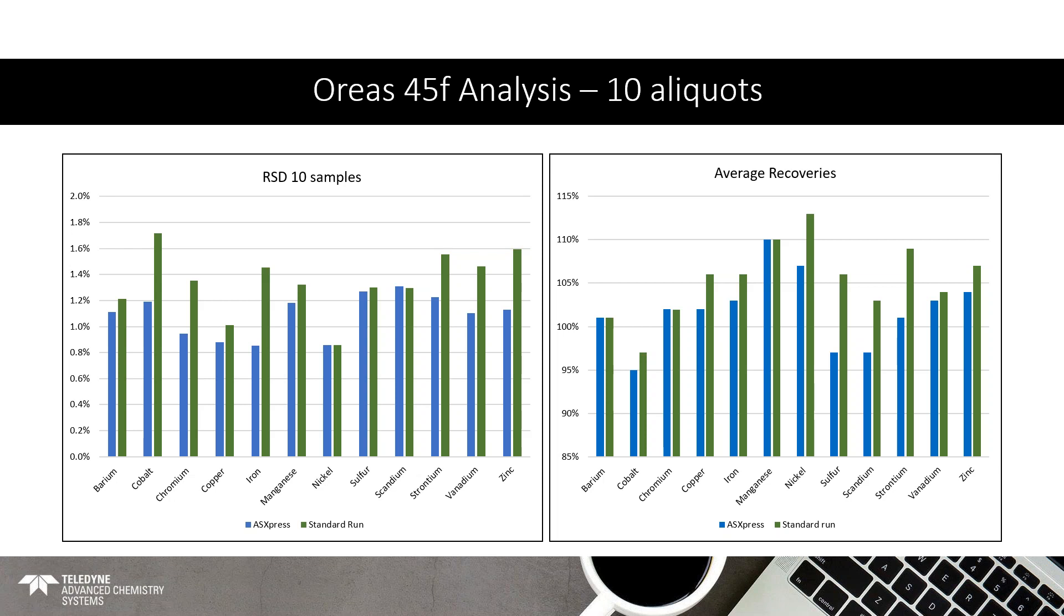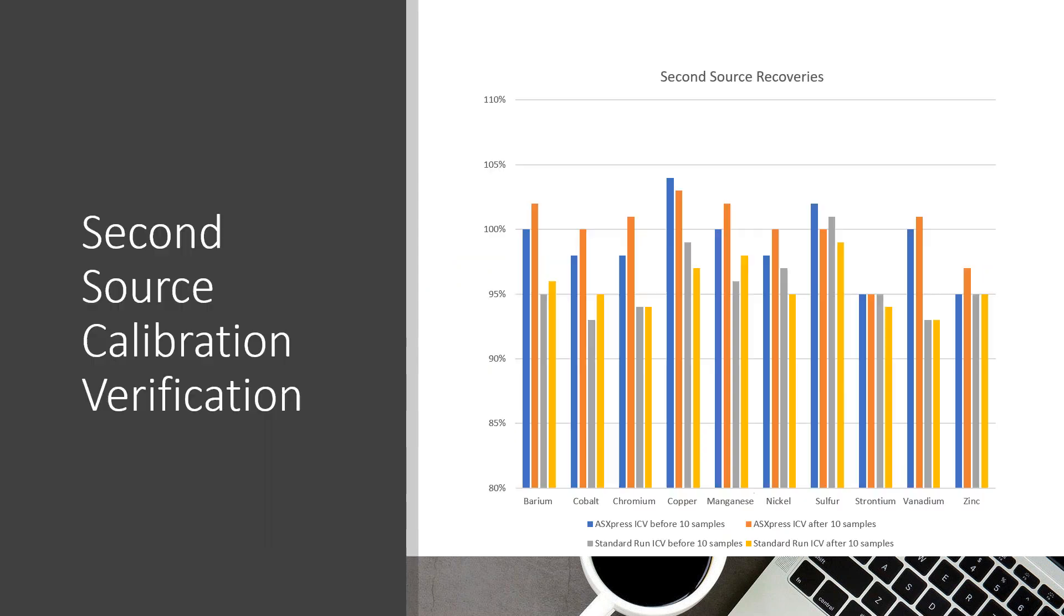And then our recoveries, again, we had the Express with the standard run. For all of those, the average recovery with the AS Express Plus is 102%. With the standard method, it was 105%. So, we're able to get slightly better recoveries and better RSDs with the additional time savings. In addition to running the samples, we also ran second source recovery. So, here's the data. And what you have here is the AS Express Plus is in the blue and the orange. That's before and after the 10 Oreas samples. And then we also compare this, the gray and yellow are our standard runs. So, for the recoveries, AS Express Plus everything came in within 5%, whereas the standard run was within 10%. So, again, slightly better, tighter data with the AS Express Plus.